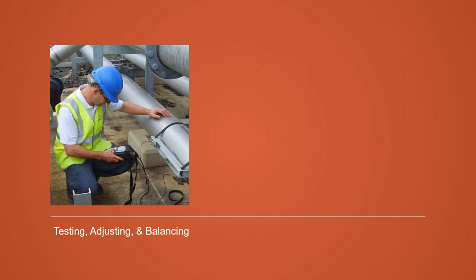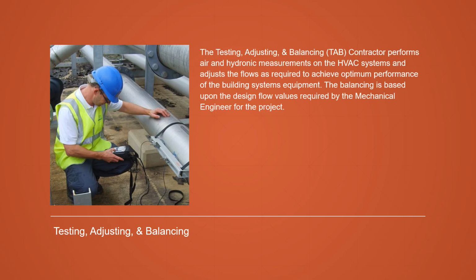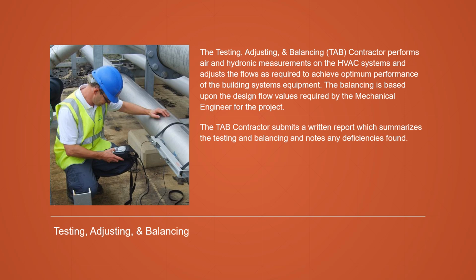A parallel process with commissioning is the testing, adjusting, and balancing of HVAC systems, also known as TAB. The TAB contractor performs air and hydronic measurements on the HVAC systems and adjusts the flow as necessary to the optimum performance and comfort levels. The balancing is based upon the design flow values required by the mechanical engineer of record for the project.